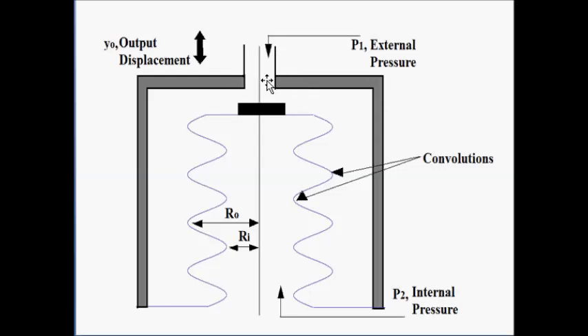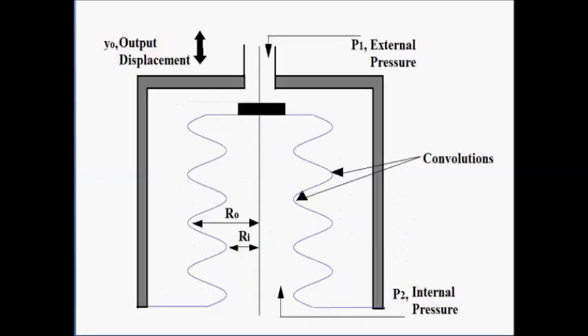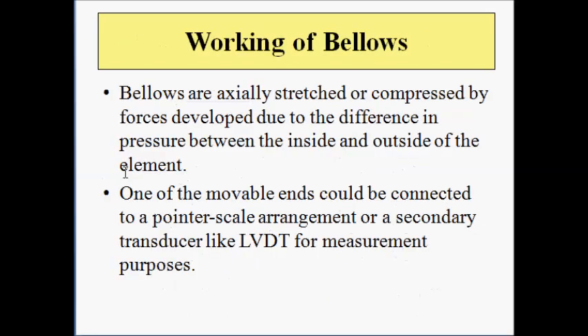When the external pressure is greater than the internal pressure, the bellows get compressed — this movable end or top end of the bellow moves downwards. This results in a displacement of the movable end of the bellow. And when the internal pressure is greater than the external pressure, the bellows move upwards and expand. So either way the bellows can either be stretched or compressed.